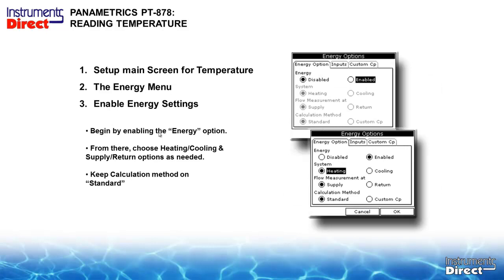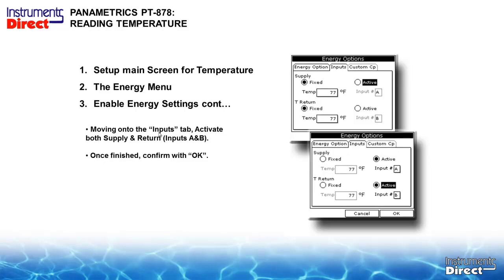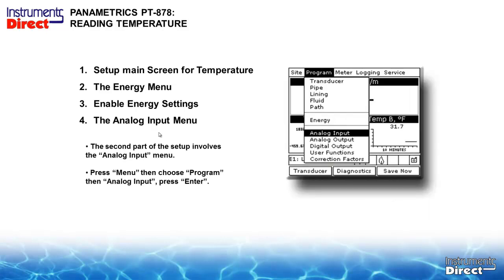Begin by enabling the energy option. From there, use heating/cooling or supply/return options as necessary. Keep calculation methods on standard. Moving on to the input tab, activate both supply and return inputs A and B, and once finished, confirm with an OK. The second part of the setup involves the analog input menu.